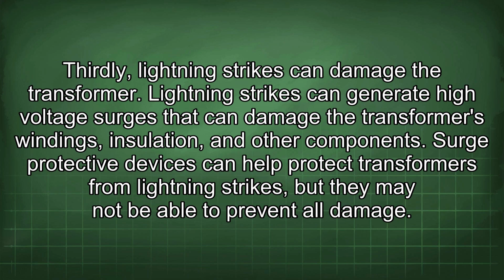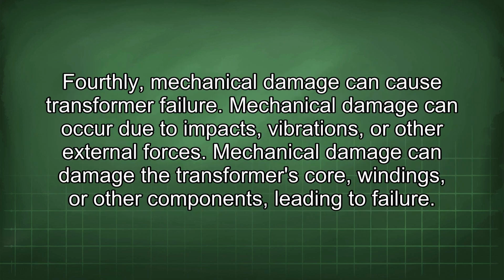Thirdly, lightning strikes can damage the transformer. Lightning strikes can generate high voltage surges that can damage the transformer's windings, insulation, and other components. Surge protective devices can help protect transformers from lightning strikes, but they may not be able to prevent all damage. Fourthly, mechanical damage can cause transformer failure. Mechanical damage can occur due to impacts, vibrations, or other external forces. Mechanical damage can damage the transformer's core, windings, or other components, leading to failure.